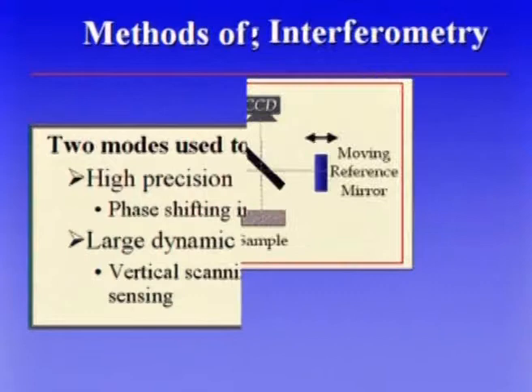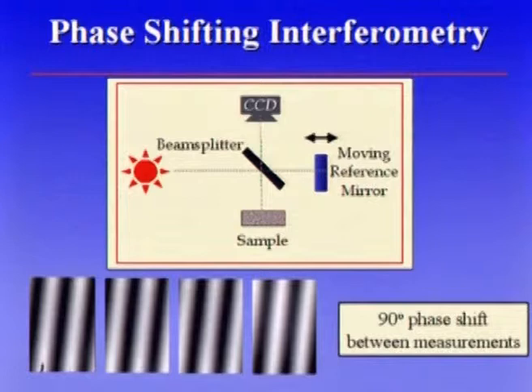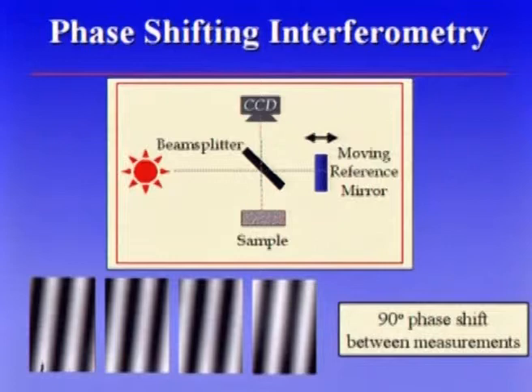In phase shifting interferometry, we take several interferograms — at least three, and for my example, four. We have these interference patterns falling on a CCD array, and we move the reference mirror, which causes the fringes to shift. We read out three or more of these patterns. Typically, we have a quarter of a fringe shift between consecutive interferograms, which corresponds to a change in phase of the two beams of 90 degrees.